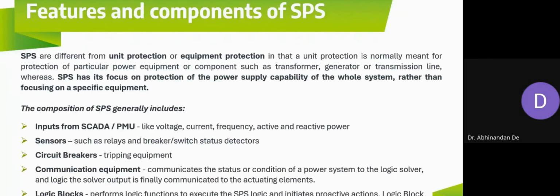So what does an SPS generally include? Typical components of the SPS include, first of all, measurement inputs. Generally the inputs come from SCADA, the supervisory control and data acquisition system. Nowadays we also use PMUs, phasor measurement units, also known as synchrophasors. They are gradually replacing SCADA, because PMUs provide dynamic variables, like voltage angles and the generator rotor angle. These measurements are possible with the PMU, which were earlier not possible with SCADA. SCADA only used to give you static variables, like voltage magnitudes, active and reactive power flow, and frequency. But nowadays, with the integration of PMUs, we also have access to the dynamic variables.